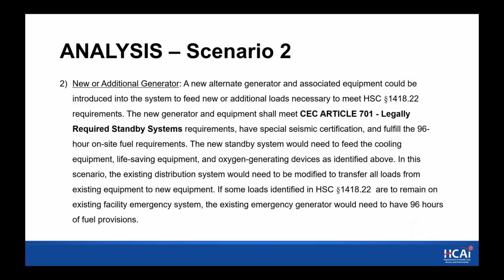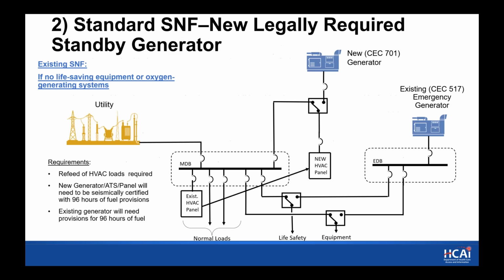Scenario 2 would be a new or additional generator that's independent of your emergency generator. We can go to the next slide, please. So in this scenario, again, all the way over to the right, we show the existing 517 emergency generator. And then you'll see on the top in the middle, we're introducing a new generator. And this generator and new transfer switch and new HVAC panel would all fall under the CEC 701 code for legally required emergency. And the requirements would be to refeed the HVAC loads from the normal to this new panel that's going to be our alternate source of power.